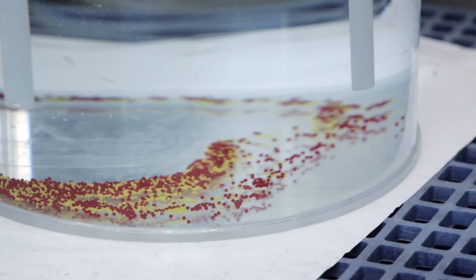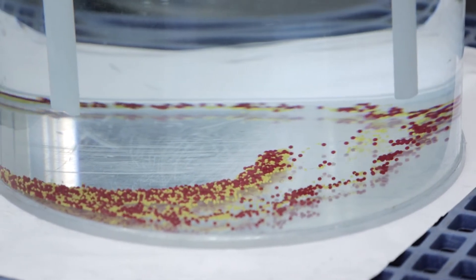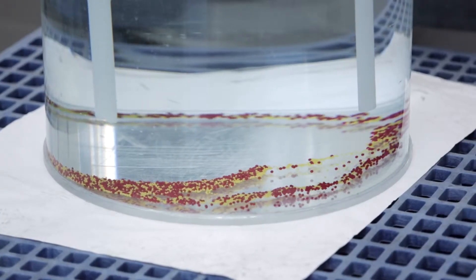You can see the feed side is not sucking them up into the pump and the return side will displace them away from the bottom but doesn't do a very good job in other areas of the drum. This is the reason that we go through and do the testing that we do in our commercialization process to determine which type of agitation is best suited for a particular slurry.